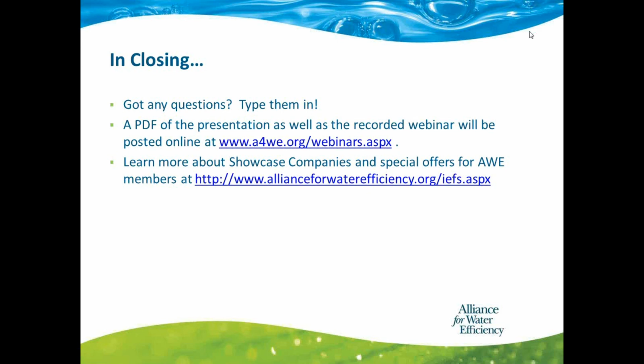Thank you. Does your product affect discharge water quality, and if so, in what way? No, we don't really have a major impact on that. There are some elements in the water that change in concentration, since we're increasing the cycles of concentration, and that will change in the discharge water. But as far as the water itself, we've worked with a number of wastewater utilities, and had them evaluate the discharge from the cooling towers, both the level of elements and the chemistries being used. To date, we haven't had any problems whatsoever. In fact, most of the utilities tell us they'd rather see what's coming from our towers than a lot of the stuff they're forced to take.